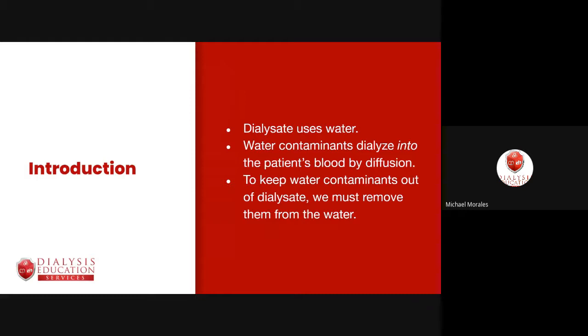We need to purify the water because any contaminants left in it will diffuse into the patient's blood, elevating their blood levels of whatever contaminant we're speaking of. This could cause complications or even death. Water has the potential to hurt all patients in a facility at one time if left untreated or used with high levels of contaminants.